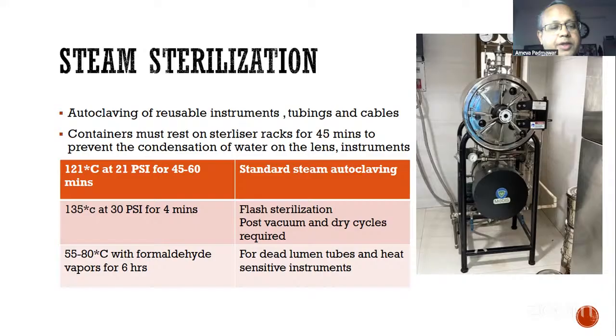Then sometimes in some centers, they have something known as flash sterilization. Flash sterilization requires a separate machine which can increase the pressure of the chamber to 30 psi, and the steam is heated to 135 degrees Celsius, and this takes 4 minutes. And of course, the post vacuum and dry cycles are required. So it takes a little more time, but it is faster than the conventional autoclaving.